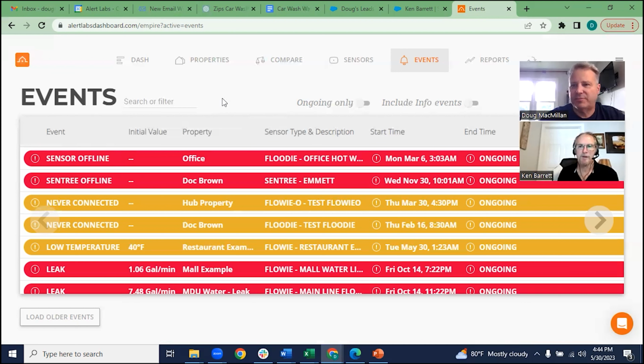If you've got something that lets you drill down minute by minute, you can look at it and say okay. Once this is hooked up, some guys check it every day as part of their routine - they look and go, I've got 10 stores, where do I need to send my maintenance guys? This one's leaking a bit of water - not a lot, probably not a stuck toilet, probably not a split pipe, but it's not at zero. So somewhere there's a valve leaking, and even if it's not a lot, it's moving water and costing you money.